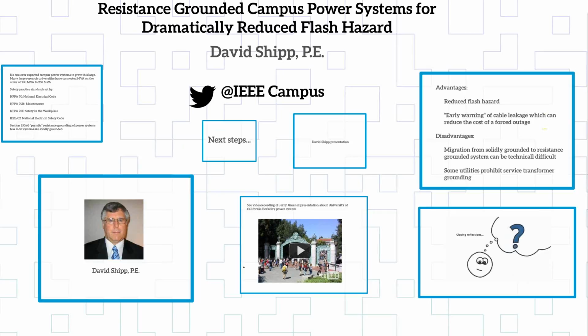At the people standpoint, you still have to dress for the PPE requirements for the three-phase fault. That's like the standard OSHA requirements and so on. But the probability of getting the incident energy anywhere near high like that is dramatically less if I make sure I follow procedures and I limit the ground fault current. Because if I limit it to a few hundred amps, I eliminate the escalation almost completely. In other words, it doesn't burn into the three-phase fault unless I leave it on seconds. You see the concept, and you can mathematically go back and get some empirical data to actually work through that.